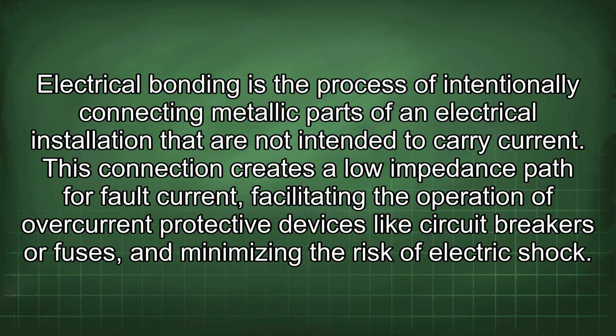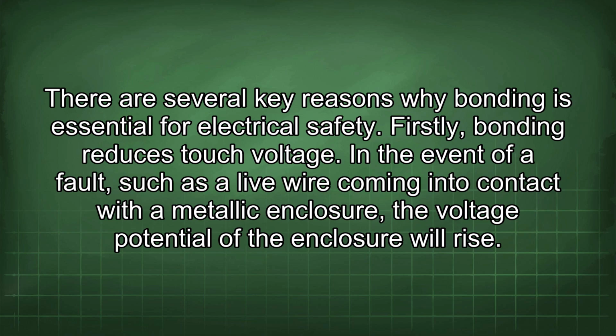Electrical bonding is the process of intentionally connecting metallic parts of an electrical installation that are not intended to carry current. This connection creates a low impedance path for fault current, facilitating the operation of overcurrent protective devices like circuit breakers or fuses, and minimizing the risk of electric shock. There are several key reasons why bonding is essential for electrical safety.